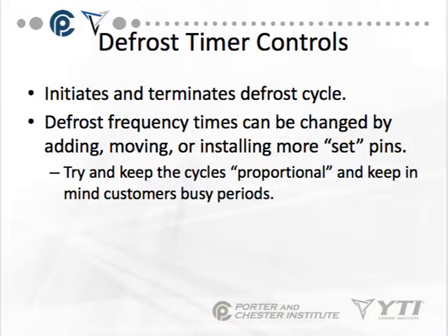We want to try to keep the cycle as proportional as possible, and you want to keep in mind customer busy periods. I do not want to put a system in defrost in a store or in a restaurant in the busiest time of the day where the door is always being opened and closed. If we do, we're going to increase the temperature of that box and put a lot more load on the system and possibly damage product.